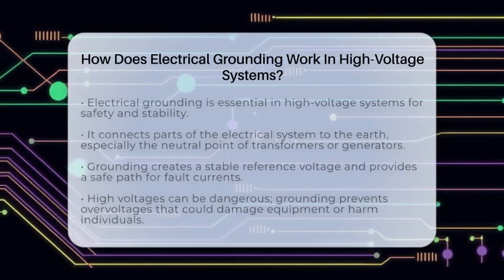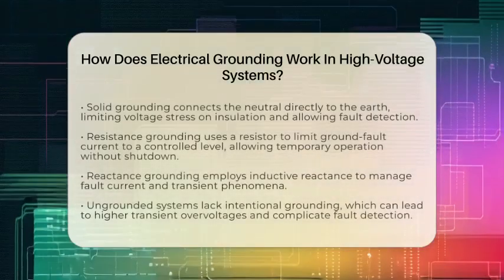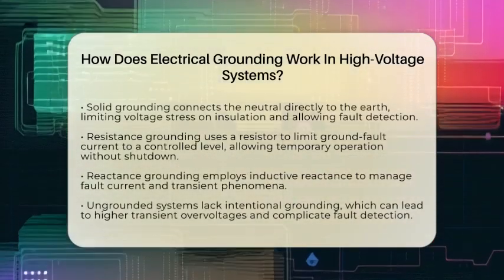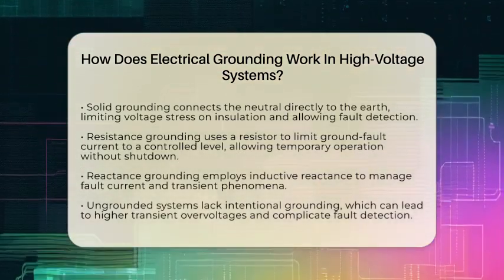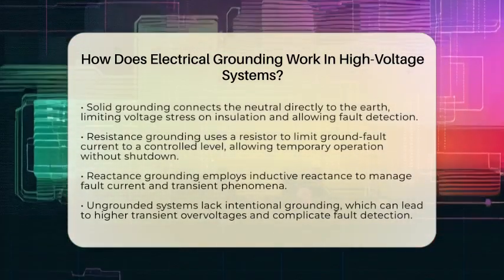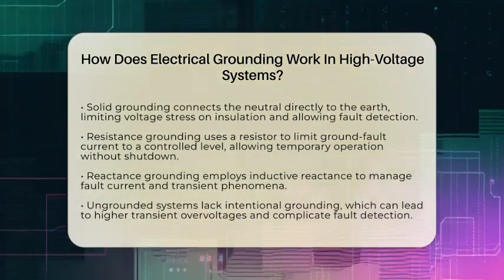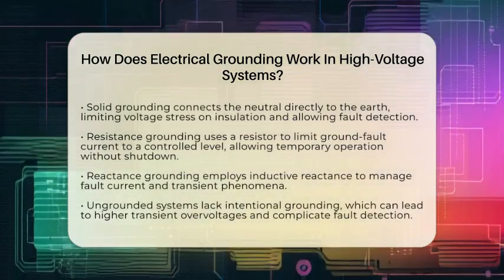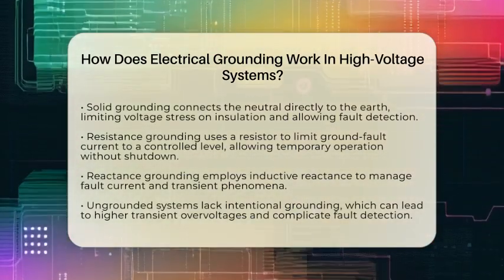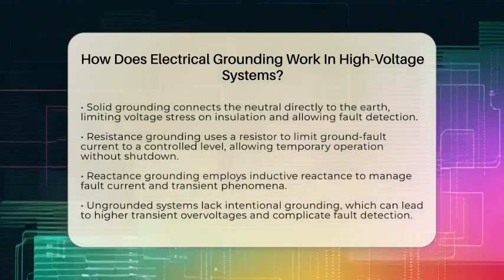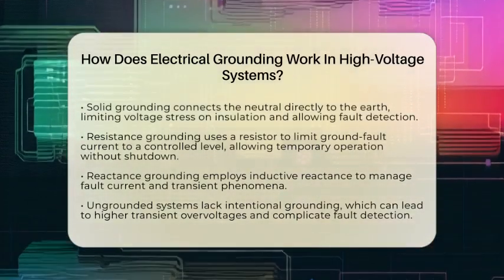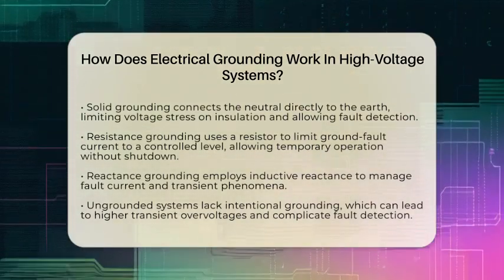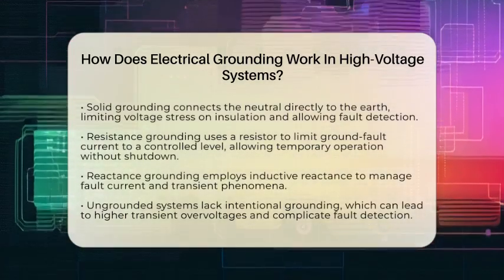There are several methods of grounding used in high-voltage systems. One common method is solid grounding. Here, the neutral is directly connected to the earth. This keeps the neutral at earth potential, which limits voltage stress on insulation and equipment. It also allows enough ground fault current to flow, enabling protective devices to detect and clear faults quickly.